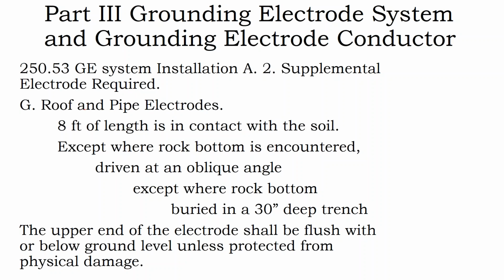So I think this should be not roof, but this should be rod and pipe electrodes. There's a procedure for determining when you can't drive that ground rod into the ground. The proper order is to first try and drive it at a 45-degree angle. And then if you can't drive it at a 45-degree angle, you need to dig a 30-inch deep trench. And the only way to dig a 30-inch deep trench, in my opinion, is to rent a trencher. Often when you're doing these kinds of dirt work projects, you're doing a ground mount array. And if you're ordering a Bobcat to help you with your ground mount augering, ordering a trencher along with that doesn't really impact your budget all that much.